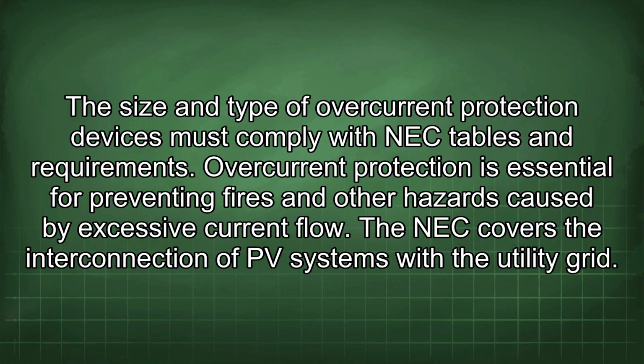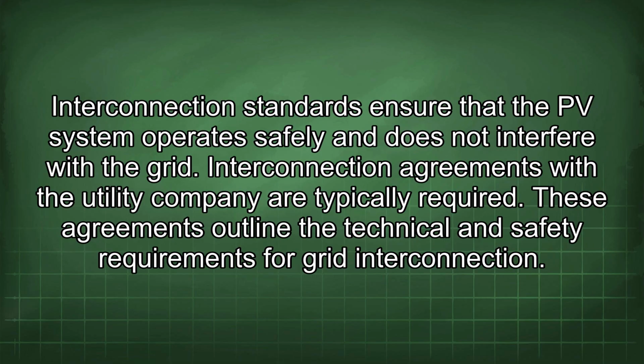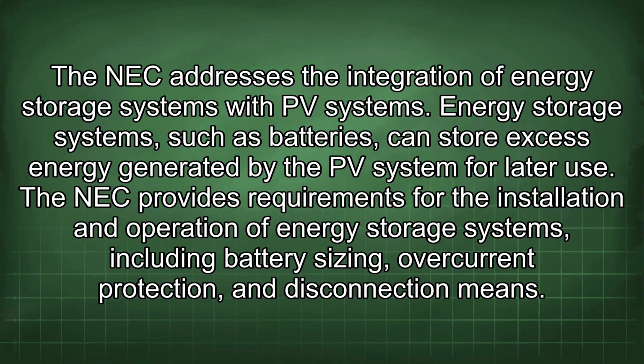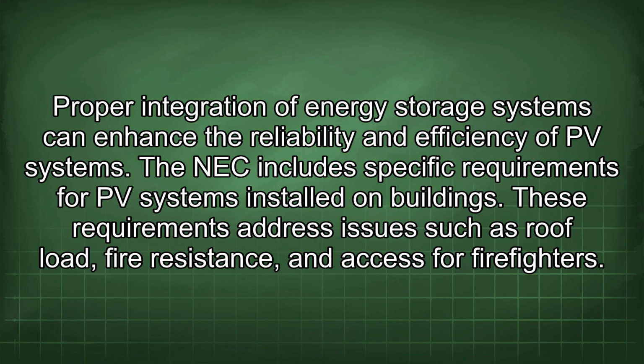The NEC covers the interconnection of PV systems with the utility grid. Interconnection standards ensure that the PV system operates safely and does not interfere with the grid. Interconnection agreements with the utility company are typically required. These agreements outline the technical and safety requirements for grid interconnection. The NEC addresses the integration of energy storage systems with PV systems. Energy storage systems, such as batteries, can store excess energy generated by the PV system for later use. The NEC provides requirements for the installation and operation of energy storage systems, including battery sizing, overcurrent protection, and disconnection means. Proper integration of energy storage systems can enhance the reliability and efficiency of PV systems.